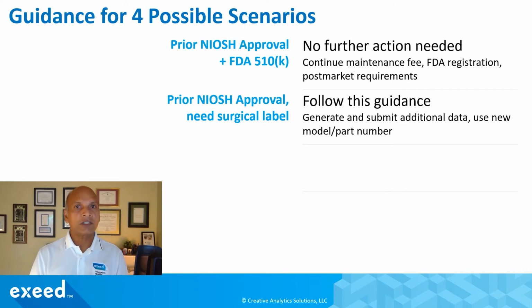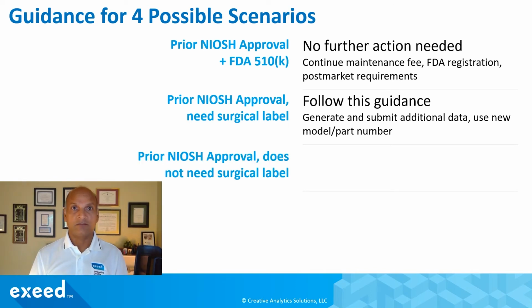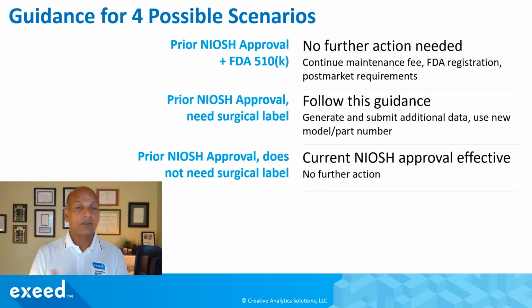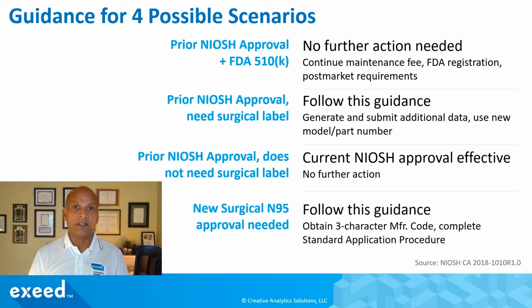But if you have prior NIOSH approval as N95, but now you need a surgical label, then you must follow this guidance. You generate and submit additional data about flammability, fluid barrier, and biocompatibility, and use a new model part number to distinguish it from an existing N95 certification. You have prior NIOSH approval, but you do not need a surgical label. Then current NIOSH approval is effective and no further action is needed. Or you have a new surgical N95 approval required. In that case, you must follow this guidance, obtain a 3-character manufacturer code, and complete the standard application procedure.